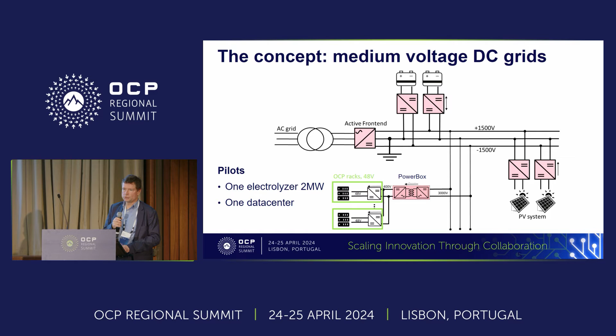The first thing, as I told you already, we avoid the losses in the UPS. There are 2 conversion steps. We avoid these conversion losses. Also, as we increase the voltage drastically, we also drastically reduce the current. And the current losses, they go with the square of the current. So this means we have really reduced losses, and we also have less copper and aluminum cables inside the data center.